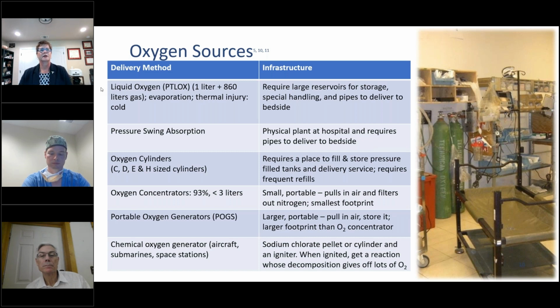When we look at these delivery methods of oxygen for the hospital, liquid oxygen is really the most cost effective. It requires storage of a cryogenic liquid in large containers and a system of pipes to deliver that transformed gas to the bedside. A more expensive oxygen delivery method is called pressure swing adsorption, and it's built into some hospitals. This too requires a system of pipes to deliver it to the bedside. And Dr. Quick will talk a little bit more about how that really works in a little bit. Some hospitals do have their own plants which extract oxygen from the air to deliver to the bedside. Oxygen cylinders, which really are the most expensive option, those cylinders that we all tend to rely on, can sometimes cost 10 times more than liquid oxygen and require much more frequent refills.